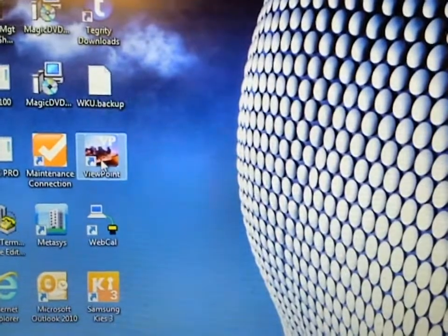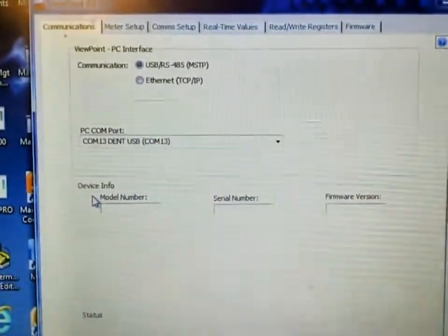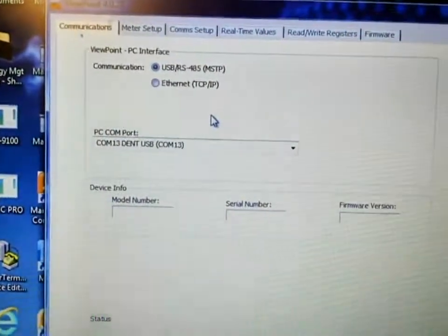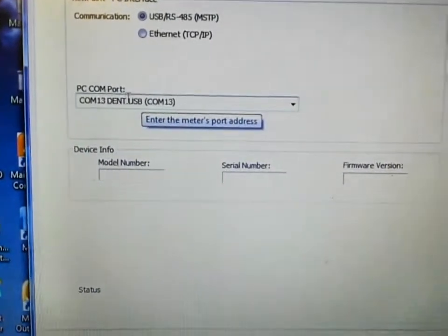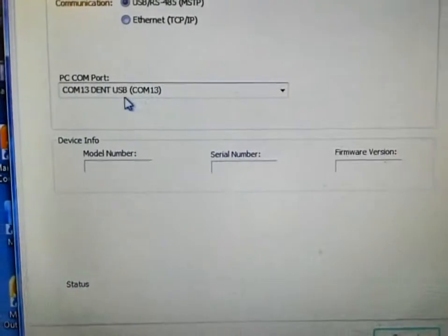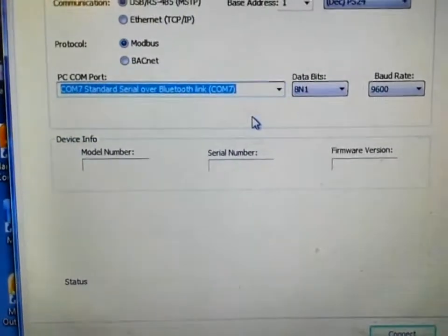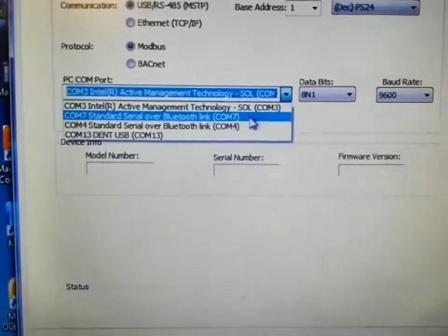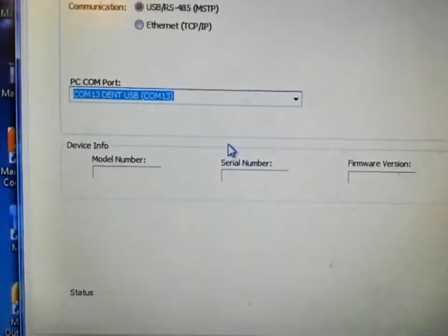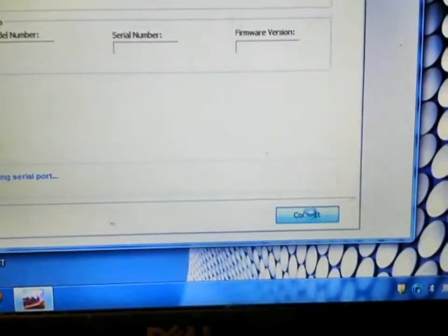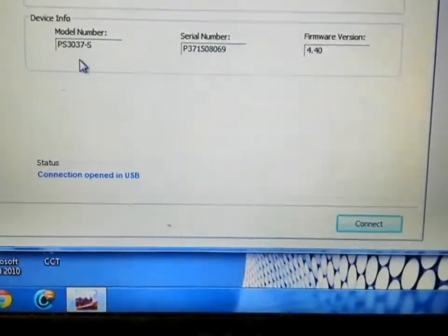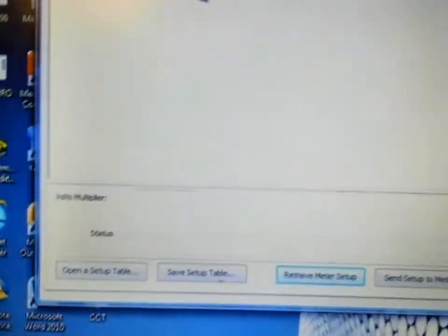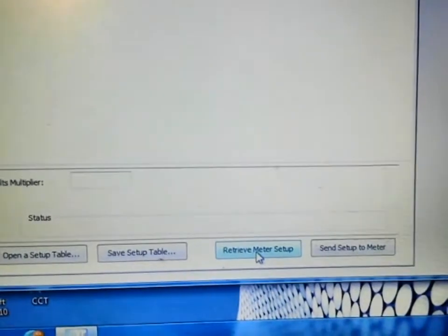Now we have the Viewpoint software installed on our laptop. I'm simply going to open the window. This is the first screen that you will come to, and this is where we will establish our communications with the meter. We are currently connected using the USB cable. In this drop-down field here, you will notice it could come defaulted as a COM port or one of the others. If you try to connect using one of those, you will get an error unless that is how you're connecting. For this device, we are connecting using the USB, so we have that selected. Once we press the Connect button at the bottom of the screen, it will populate these three fields with the model number, serial number, and firmware version for your meter. The next step is to open the Meter Setup tab, go down towards the bottom of the screen, and press Retrieve Meter Setup.